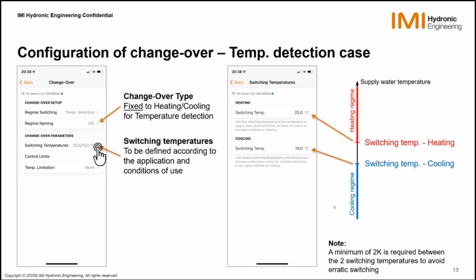One good thing to remember, but you will see that because the app will not allow you to do anything else, is that you need to have a minimum of 2 kelvins of difference between the two switching temperatures. And this is to avoid any erratic switching that could happen over time. If you are in mid-season, you would not like the valve to constantly make a switch, even if it is only in the logic of the valve because it's not operating, it's in between. It's never good to get the system constantly switching from one to another because you never know what can be related in terms of reading the current regime by bus and then doing a specific action that could induce some trouble in the rest of the control system.